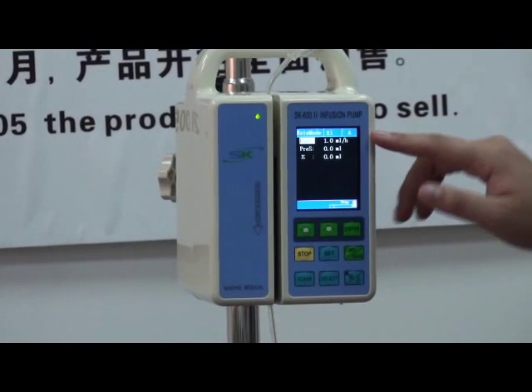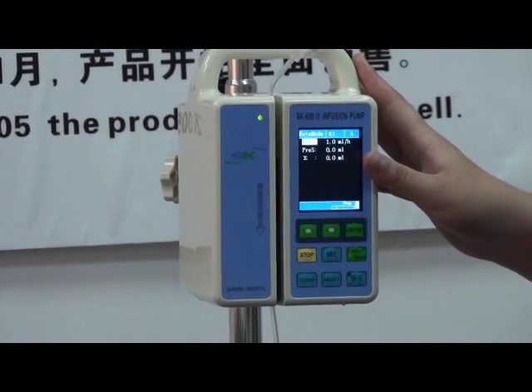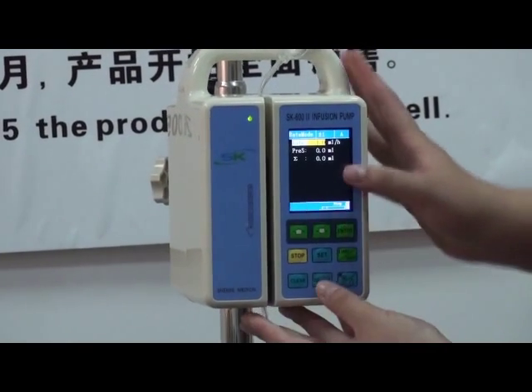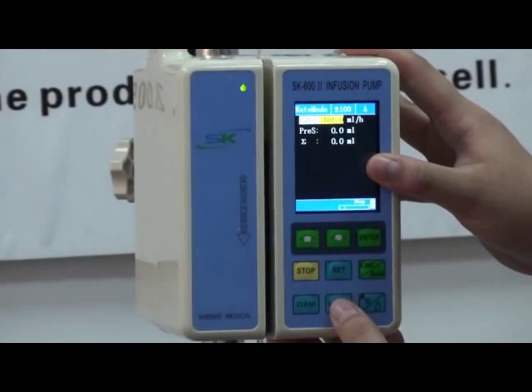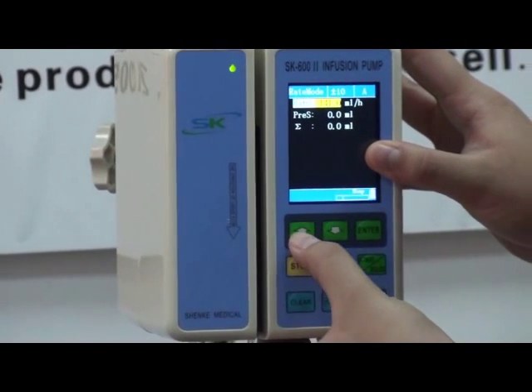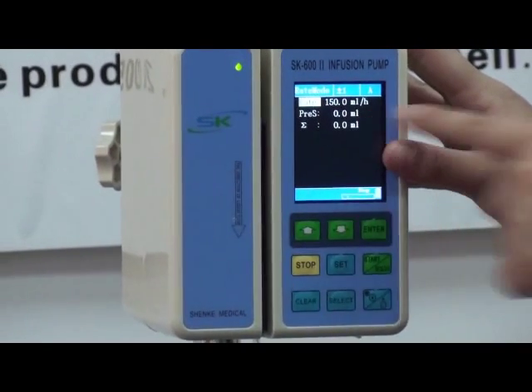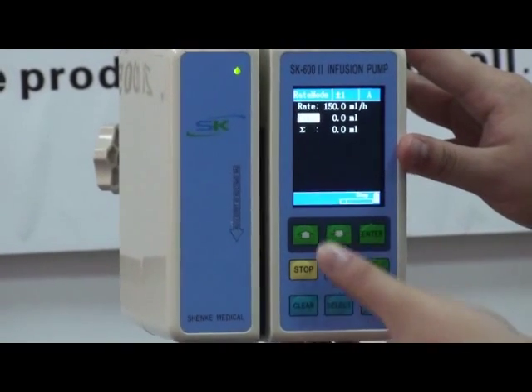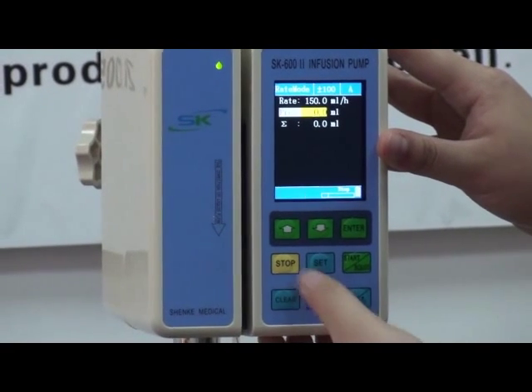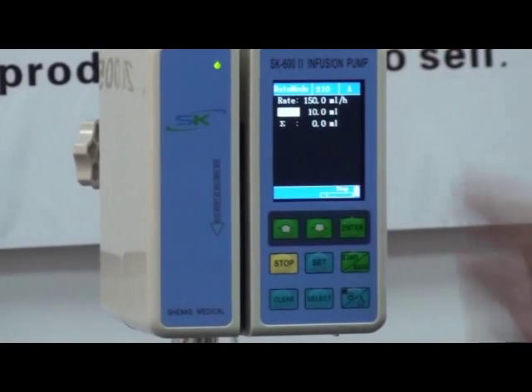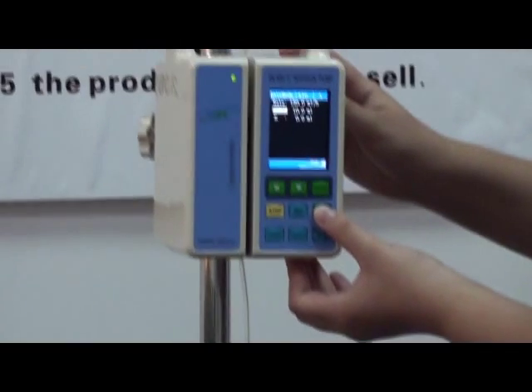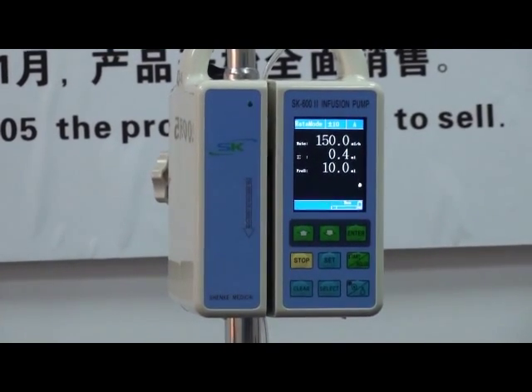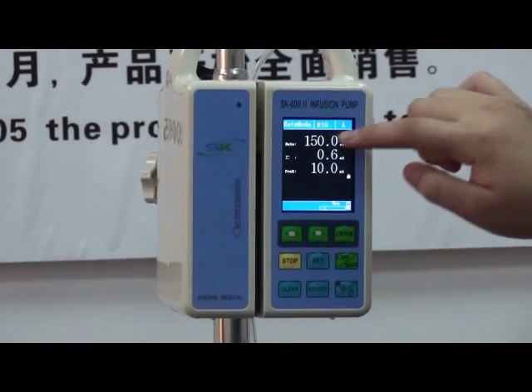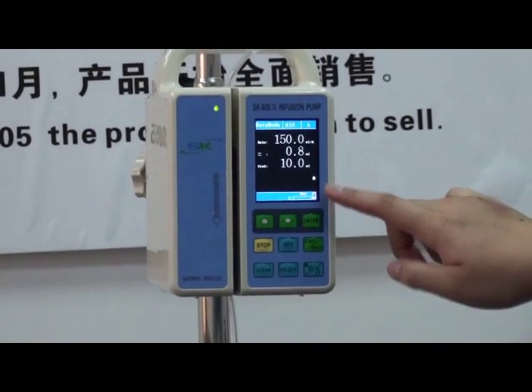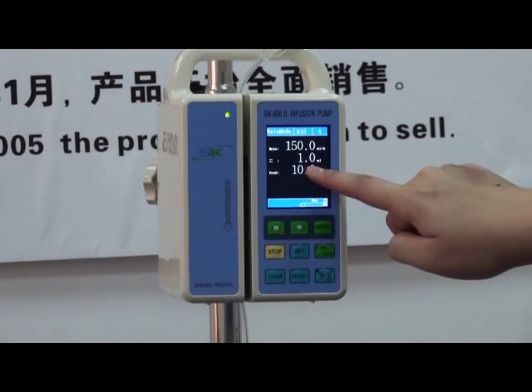Okay, this is rate mode. Then you change the rate to be 150 ml an hour. Okay, 150 ml per hour. The preset volume to be 10 ml, and open this. After that, press Start key to start the pump. Now you can see the light is flashing and the infusion pump is working at 150 ml per hour for infusion. This represents the accumulated volume. Now it's increasing.